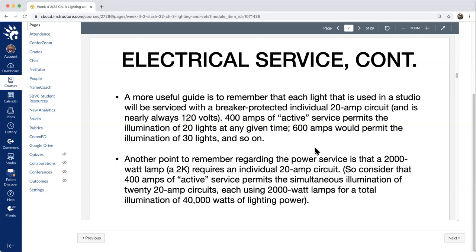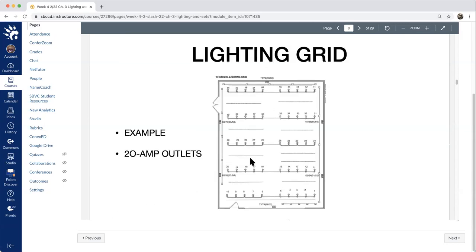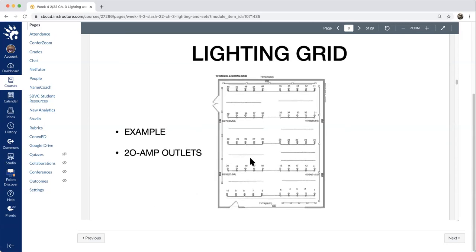A more practical way to think about it: each light used in the studio is usually serviced with a breaker-protected individual 20-amp circuit at typically 120 volts. The 400 amps of active service permits the illumination of roughly 20 lights. A 2,000-watt lamp requires an individual 20-amp circuit. So those 400 amps of active service — 20 circuits each using 2,000-watt lamps — gives a total illumination of 40,000 watts of lighting power. This is why studios are designed the way they are, with all these fail-safes in place to prevent surges or fires.